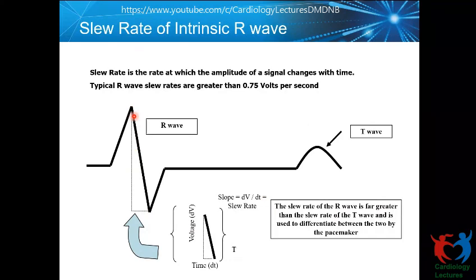If it is higher, then the frequency is higher. But let's say in a T wave, it is changing slowly, so the frequency is lower. So the slew rate is related to the frequency of the waveform. Higher slew rate relates to the higher frequency, lower slew rate refers to the lower frequency. So pacemaker electronics have a filter. We want to filter out all the unwanted waveforms. Typically, we want to filter out myopotential if it exists. We want to filter out the T wave also. The T wave has a lower frequency. Myopotentials typically have a higher frequency.